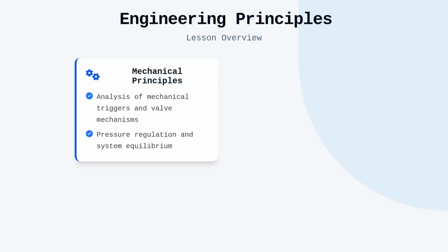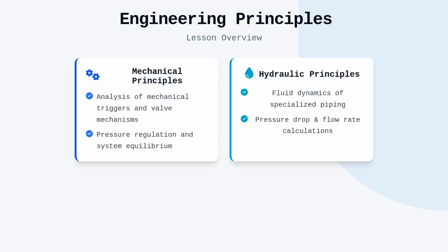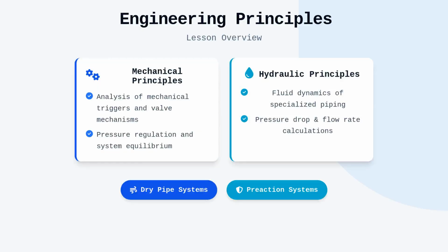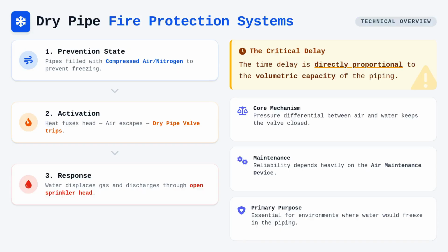Welcome back. In this lesson, we will examine the mechanical and hydraulic engineering principles governing dry pipe and pre-action sprinkler systems. Dry pipe systems serve as the primary defense in environments where ambient temperatures are insufficient to prevent the freezing of water-filled pipes. Unlike wet systems, the piping network downstream of the dry pipe valve contains compressed air or nitrogen rather than water. When a sprinkler head fuses, the sudden drop in pressure causes the dry pipe valve to trip, introducing water into the system.